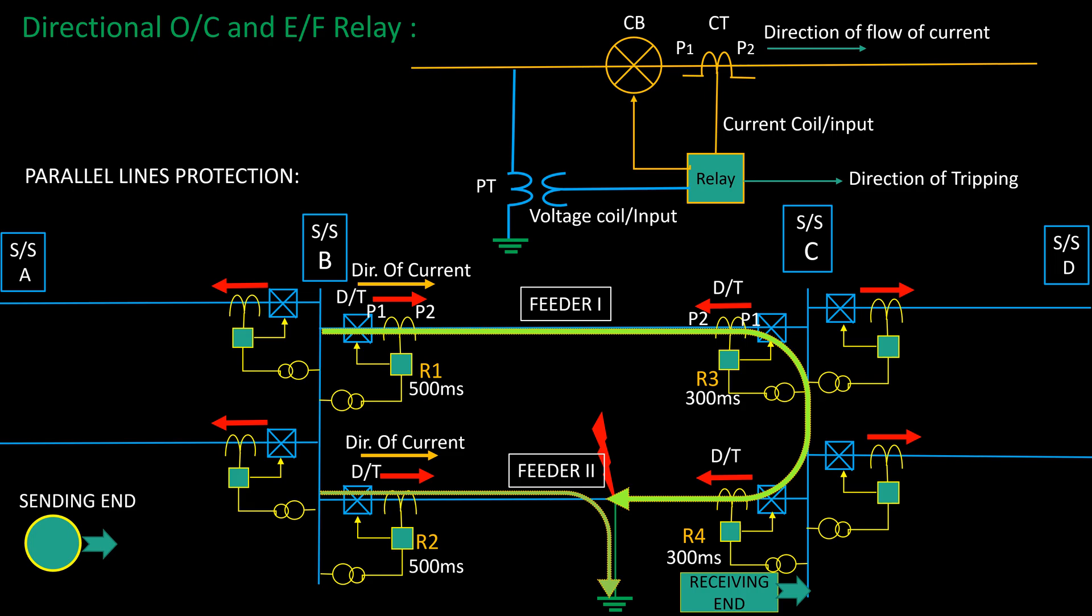Again, this fault current uninterruptedly reaches at the fault point, facing relay R4 where direction of flow of fault current is same as the direction of tripping of the relay, and the relay R4 issues a trip of the respective circuit breaker.